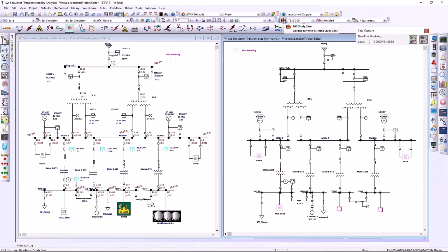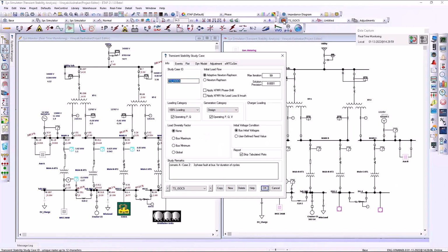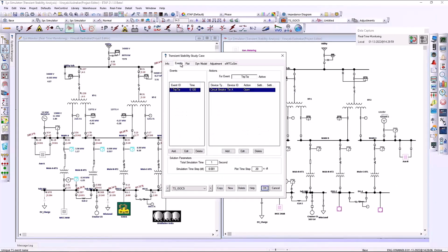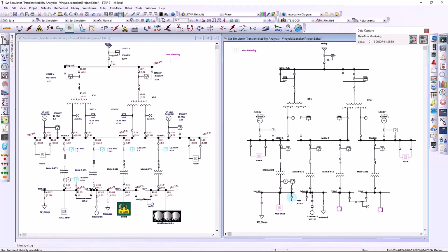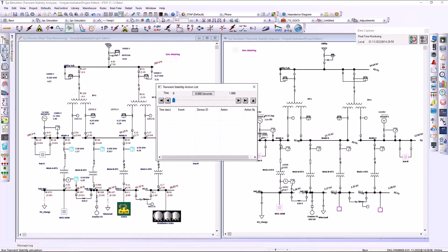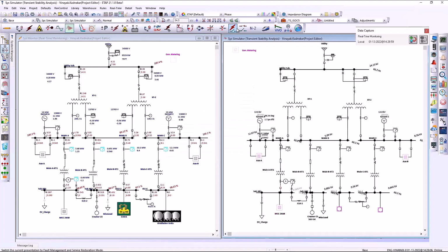On another demo, we can run a transient stability study case to observe how it affects coordination on breakers. In this scenario, using live conditions, we will simulate the trip of a tie circuit breaker after 100 milliseconds. As you can see, this also causes circuit breaker 2A1 to trip because of an overcurrent.